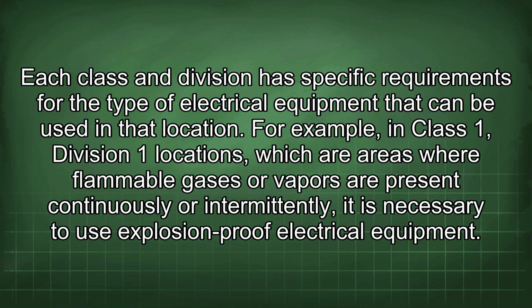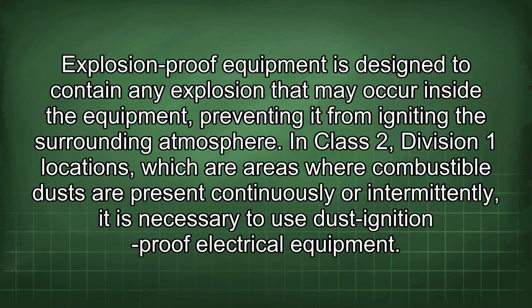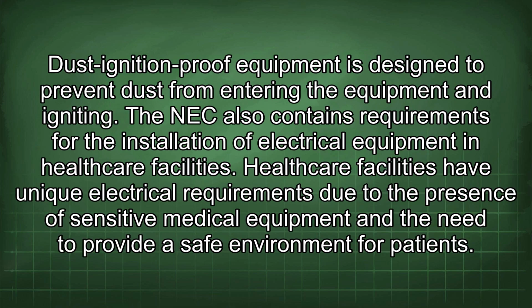For example, in Class 1, Division 1 locations, which are areas where flammable gases or vapors are present continuously or intermittently, it is necessary to use explosion-proof electrical equipment. Explosion-proof equipment is designed to contain any explosion that may occur inside the equipment, preventing it from igniting the surrounding atmosphere. In Class 2, Division 1 locations, which are areas where combustible dusts are present continuously or intermittently, it is necessary to use dust ignition-proof electrical equipment. Dust ignition-proof equipment is designed to prevent dust from entering the equipment and igniting.